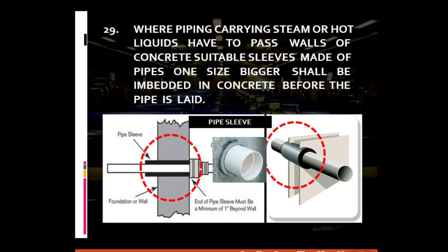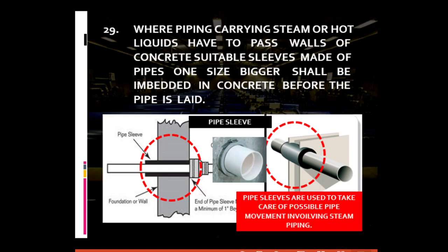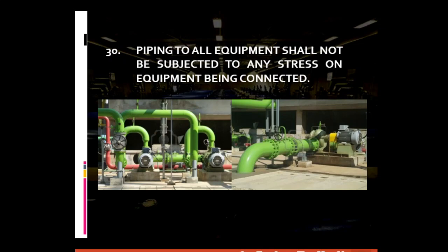A pipe sleeve is used to accommodate thermal motion or thermal movement, preventing the buildup of thermal stress. For general piping requirement number thirty: piping to all equipment should not impart any stress on the equipment being connected. Machines or equipment to which pipes are connected are more expensive than the pipes themselves. Thus, there should be no unnecessary stress — by way of vibrations — coming from the pipes that could affect the machines. Specialized kinds of piping supports that take care of any unnecessary loads, forces, or movements are used, as shown in general piping requirement number two.